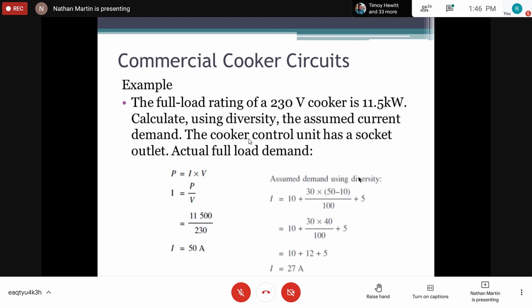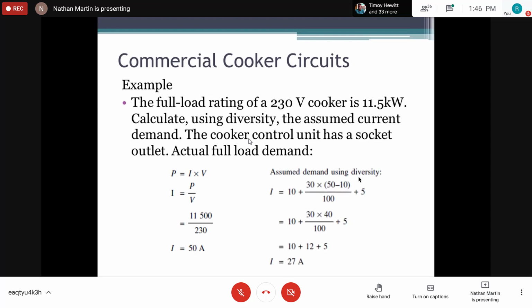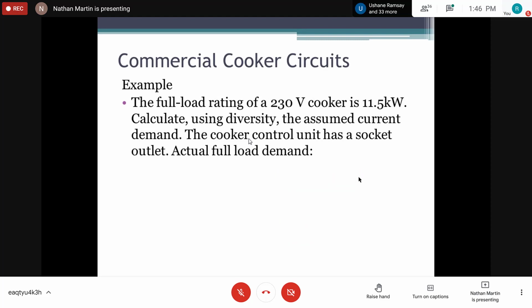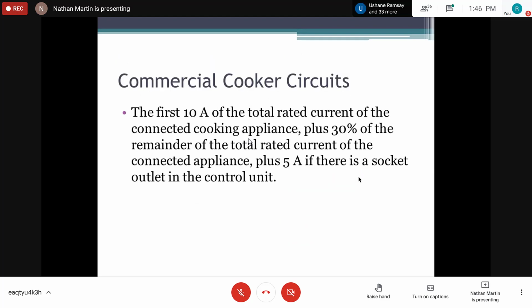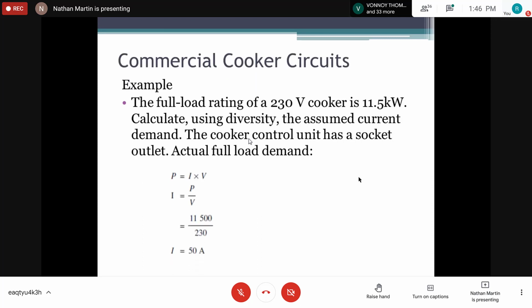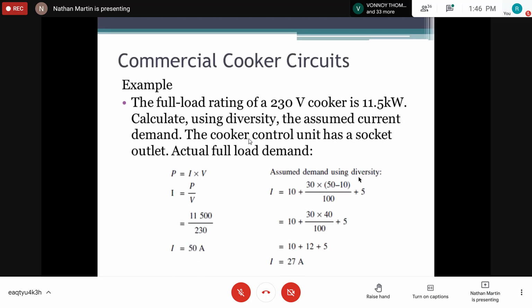So applying the diversity factor, remember we say the diversity factor is 30%, right? And so we find 30%, we subtract off the remainder. So we add 10 amp. So that is why we have 10 amp here. So we have 10 amp plus 30% of the remainder. So this is finding 30% of 40 amp, right? And then add 5 more amps, right? And the total of that will be what our cooker will use to select our cable size, right?